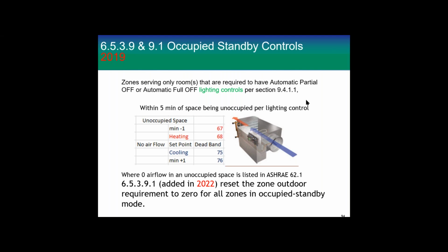So if you've got the lighting controllers in there, and they're going to send a signal to say this room is not occupied, within 5 minutes of it being unoccupied, you have to reset the dead band up 1 degree or down 1 degree, whether you're in heating or cooling. Now, when you're in dead band, you can go to zero set point if this space is listed in the 62.1 ASHRAE. There's tables. I think they've done it a little different now, but they used to have asterisks, and they have the same information. But anyway, it'll say these spaces are allowed to go to zero set point when unoccupied. And we work together with them, and they don't care about the carpet laying on the floor. It's based on occupancy, and you can shut it completely off, because we debated it a long time with them. So that box can go to zero set when it's in dead band between those numbers.